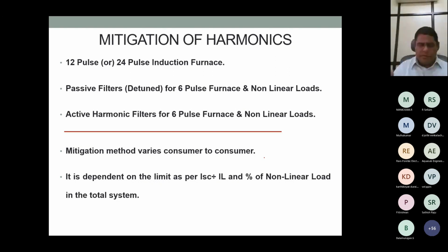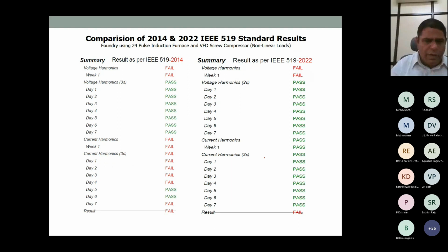For example, if his limit is 12% and his measured TDD is only 13%, 1% excess, he can either install an active harmonic filter of lower capacity or a detuned filter, and he can come out of the issues. So it is dependent on the consumer. This one I would like to share with people. I am very happy to share this slide.